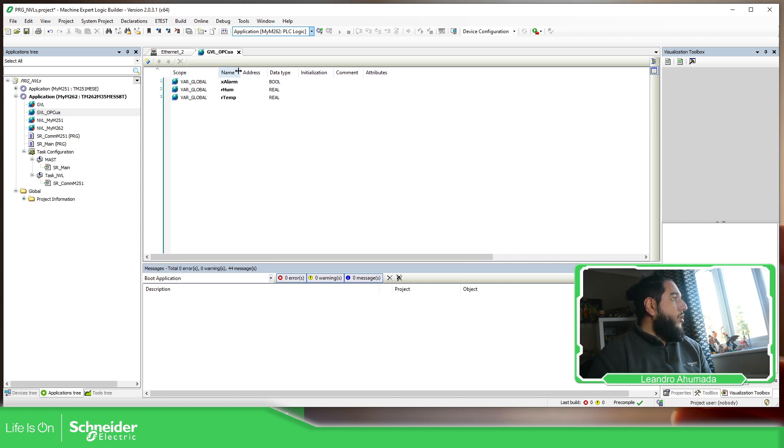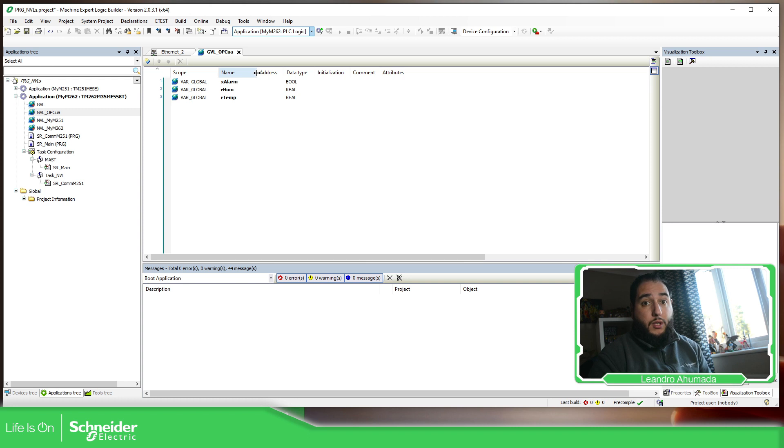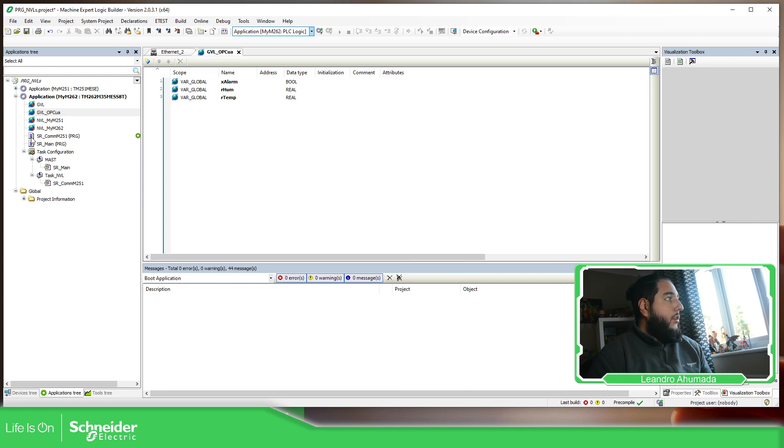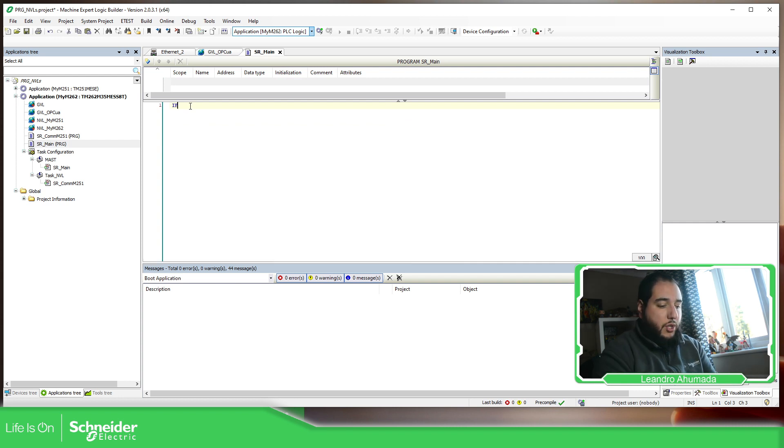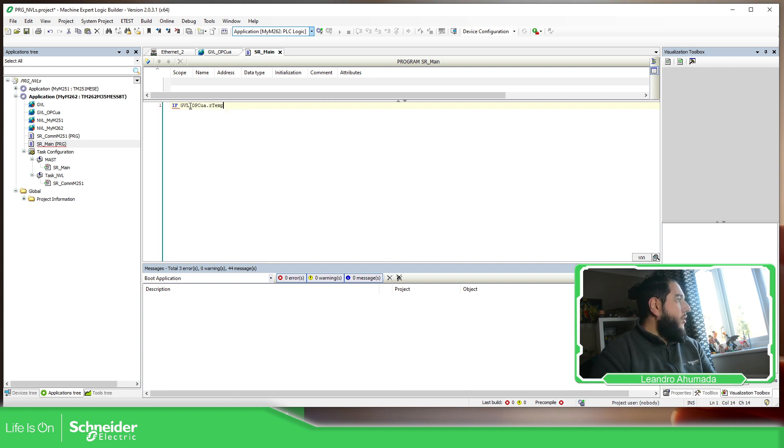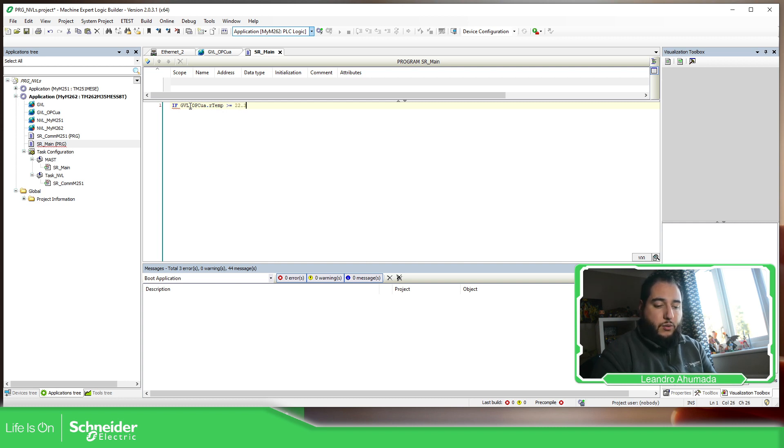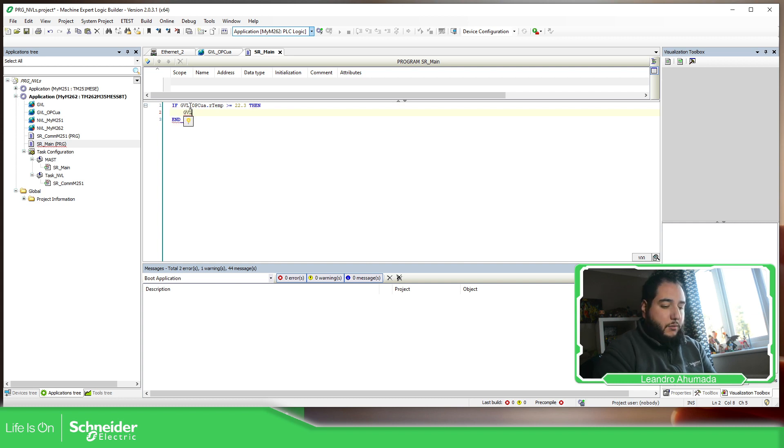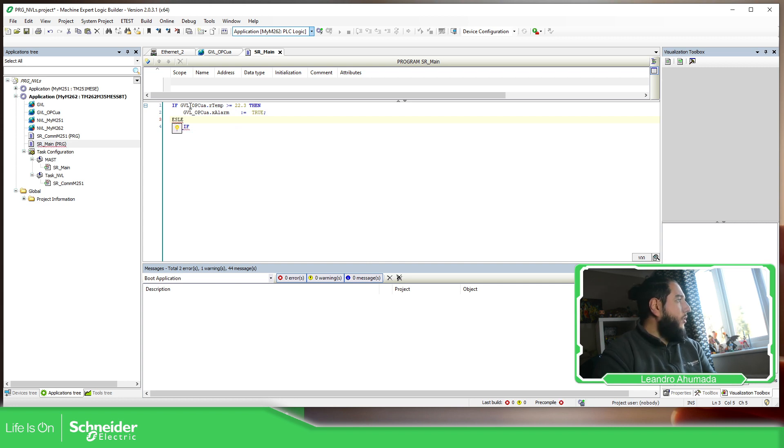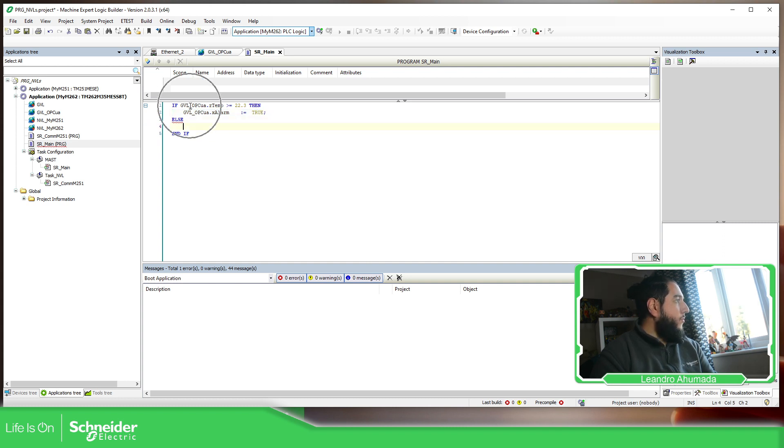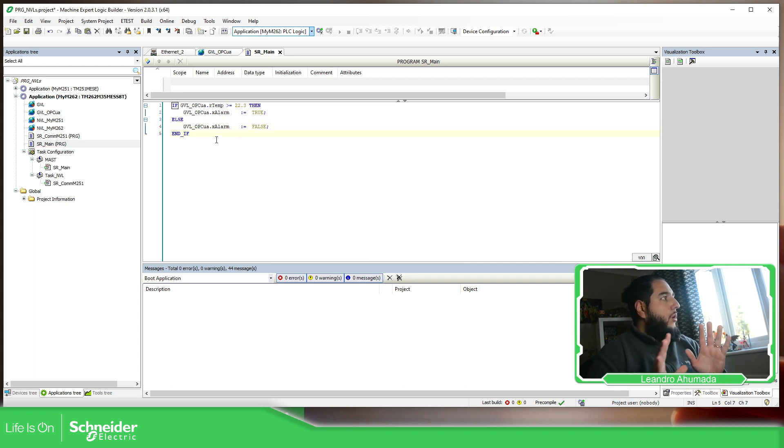As soon as you define the variables that you're going to share with the OPC UA client, what we need to do is use them, at least one of them, on one of the POUs. So I'm going to do a small logic. If the GBL_OPC_UA dot temperature is higher than 22.3, then the GBL_OPC_UA dot xAlarm is going to be true. Else, this value is going to be false. Just to add something that you can see that it's working. So we have created our logic for this.